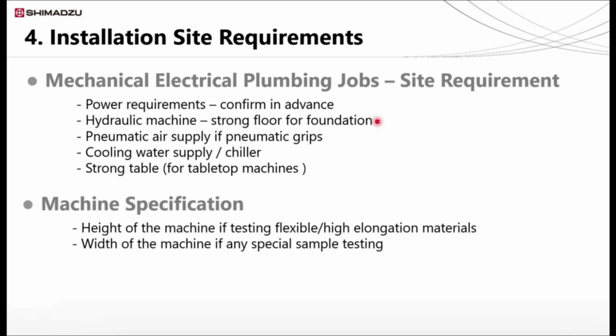Important point: a hydraulic machine may need a strong concrete floor foundation. So discuss the foundation requirement in advance and make sure the site is ready for installation. If any pneumatic accessories are purchased, either purchase a compressor additionally or arrange the pneumatic air supply in the lab. Sometimes cooling water supply is required for some machines. For example, some hydraulic grips or high temperature extensometers might need cooling water supply. In such cases, make sure the chiller is purchased additionally or ensure the cooling water availability in the lab.